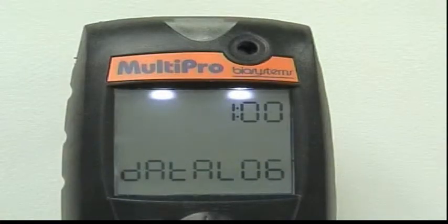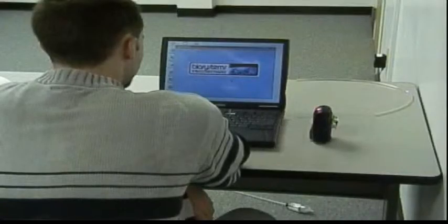If your MultiPro includes the data logger upgrade, the current data sampling interval will be shown in minutes with the word data log. At the default data log sampling interval of 1 minute, the MultiPro will store approximately 41 hours of data before it begins to write new data over the oldest data. The sampling interval can be modified with Biosystem's BioTrack program using a PC with an IRDA port, or the sampling interval can be modified directly with the mode button on the instrument. Direct programming options are covered in the MultiPro reference manual.